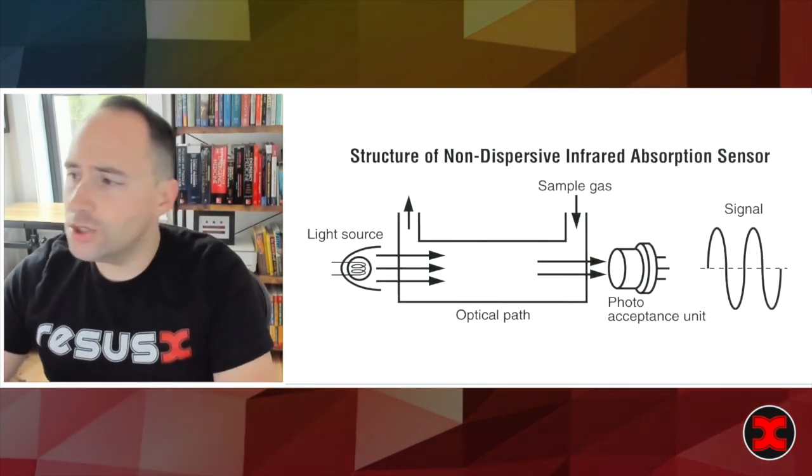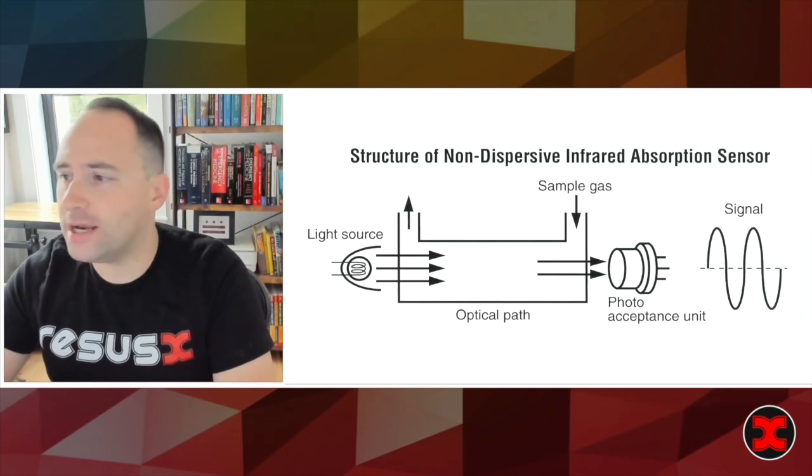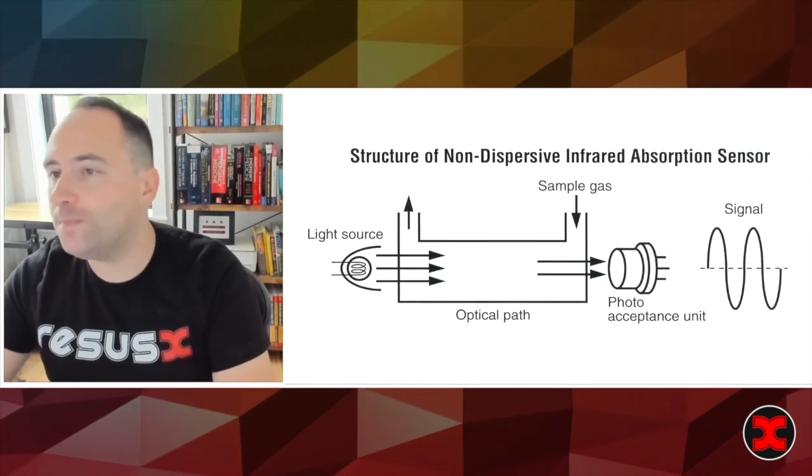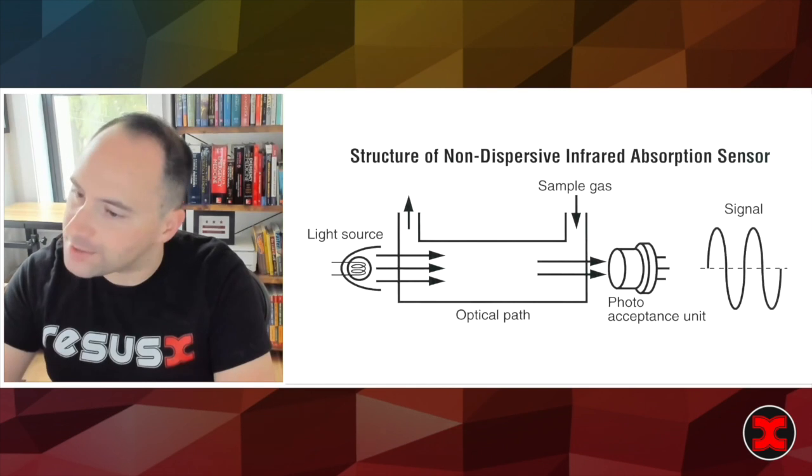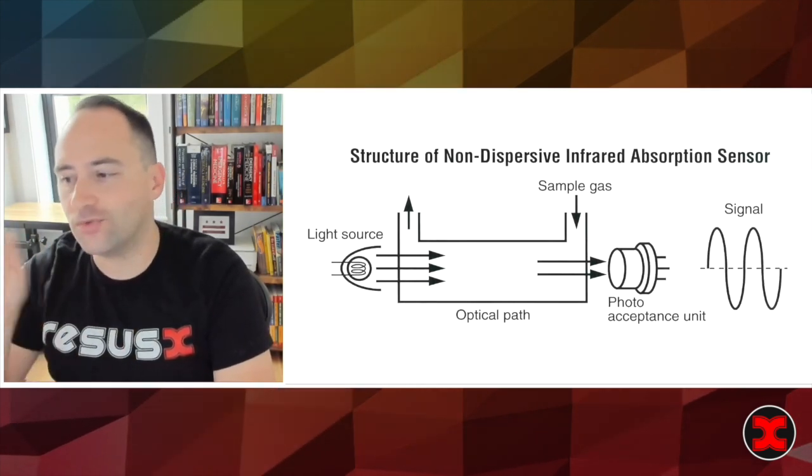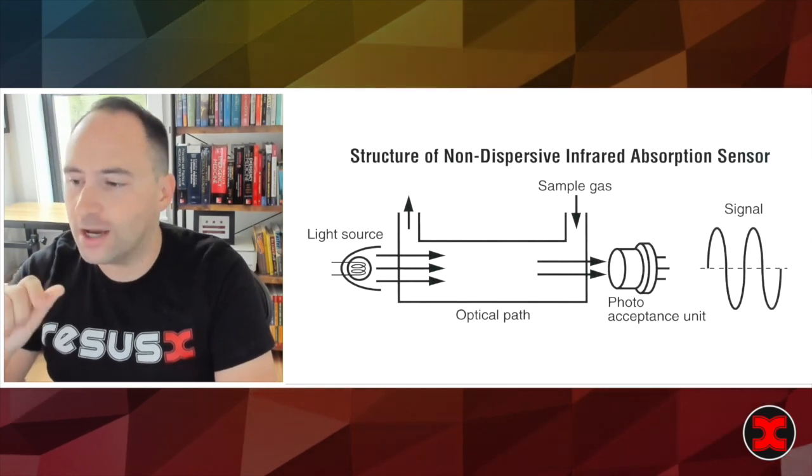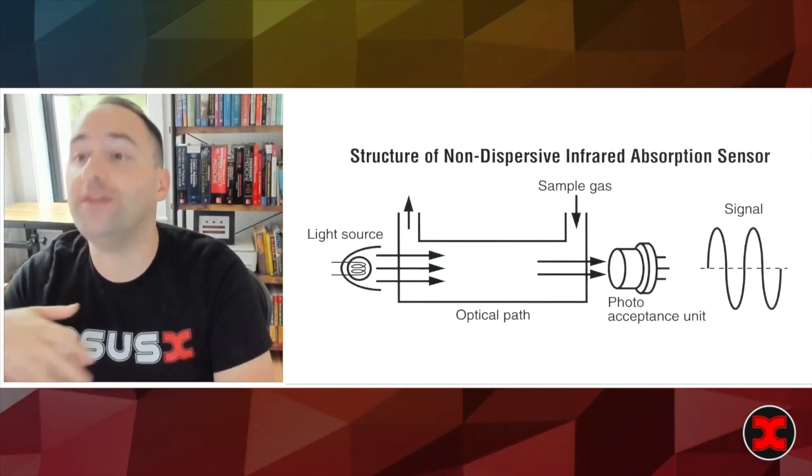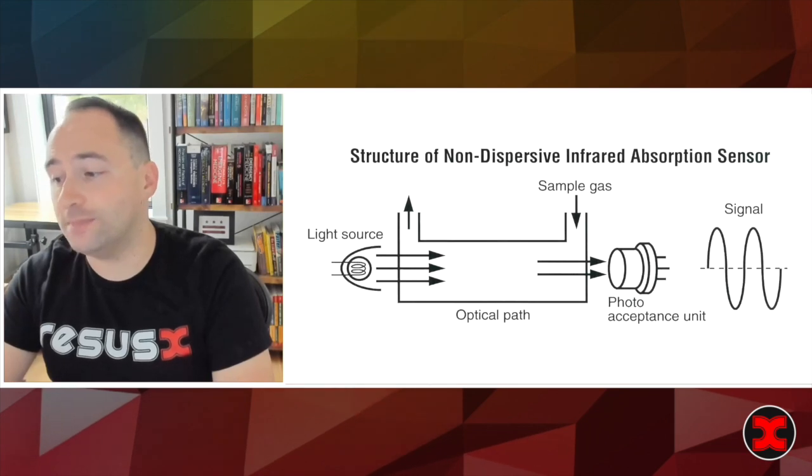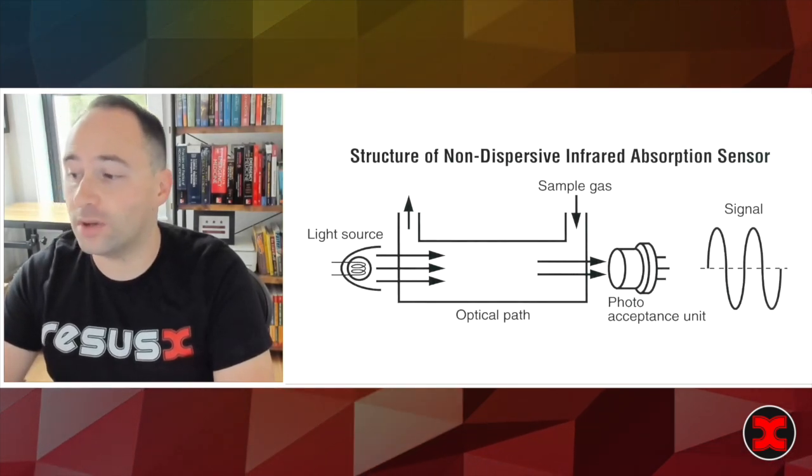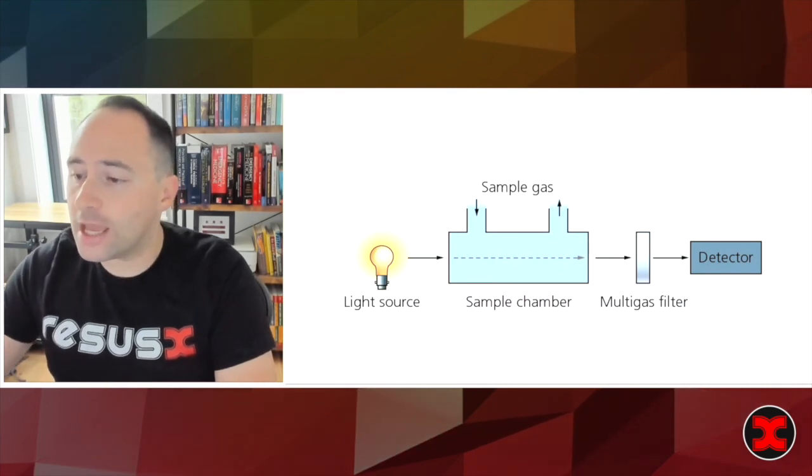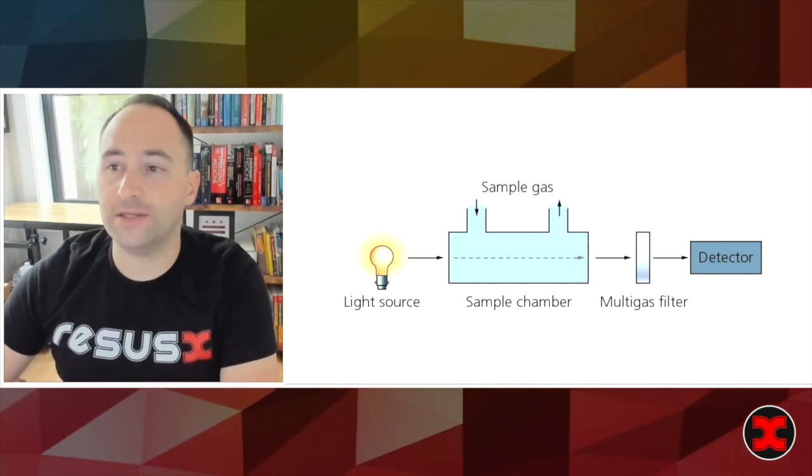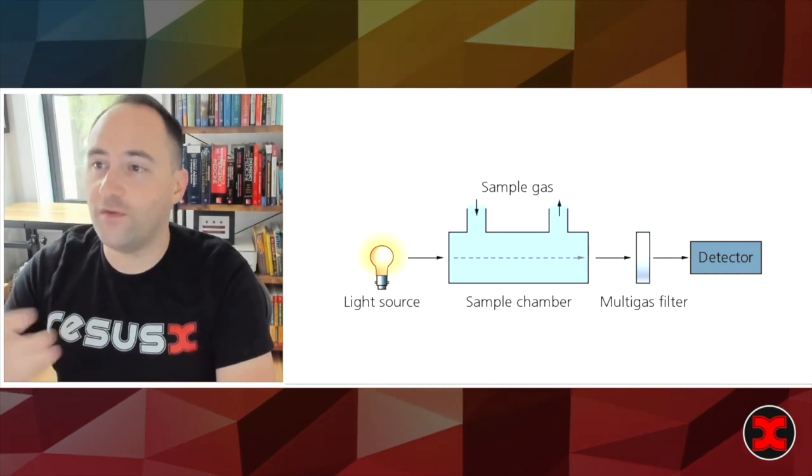So how does this work? The way that modern end tidal works is by non-dispersive infrared absorption and this is actually a pretty simple concept with a fancy name. A beam of infrared light passes through a gas that your patient exhales and the resulting intensity of the transmitted light is then directed to a photo detector. So fun fact, CO2 absorbs light around 4.26 micrometers and as more CO2 is present in the exhaled gas, more infrared is absorbed at this wavelength and therefore less will get to the detector. In other words, the more CO2 that's present in your patient's exhaled gas, the more infrared light is absorbed and this is graphically represented on the screen as the waveform that we all know and love.